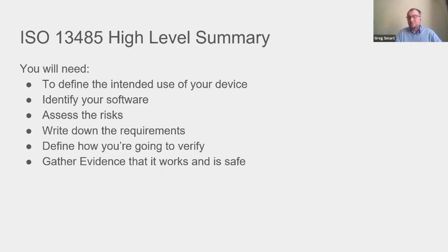And because a release note can be a controlled document in your document management system, you can demonstrate that it went through an approval process, so it was released in a controlled way. You can include in your release note things like the evidence that the testing was done to satisfy the verification requirements, and so on and so forth. So the release note is really important.